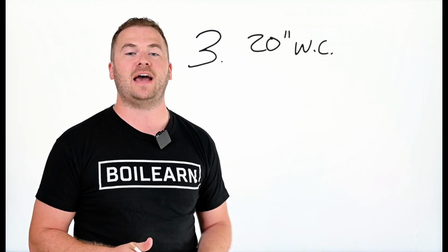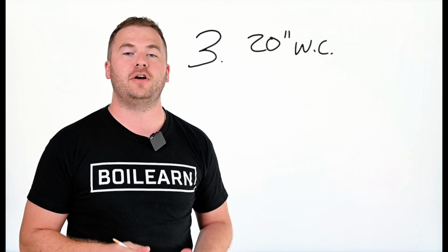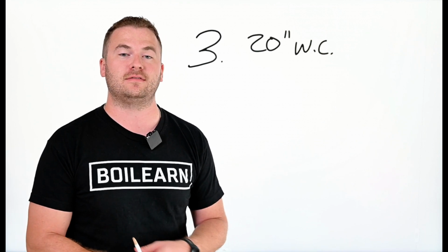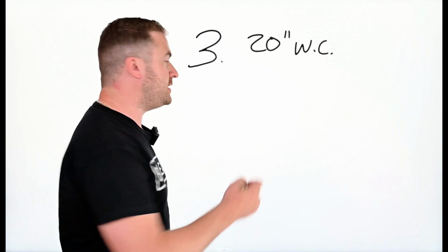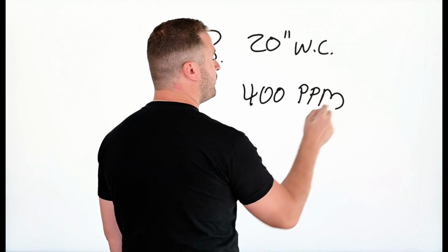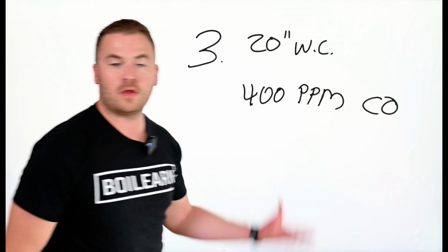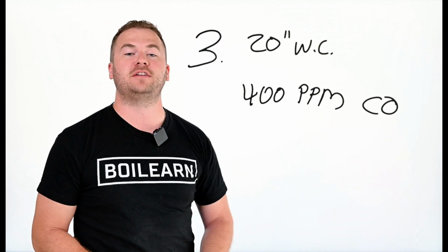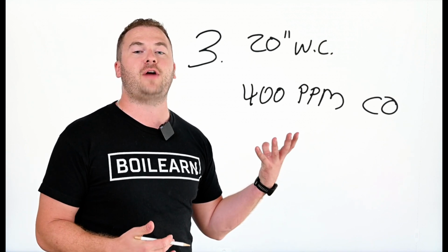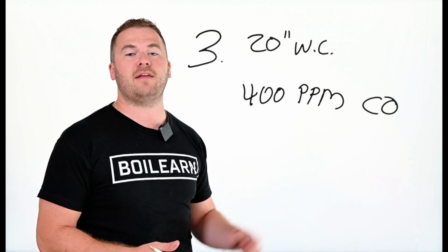for the inlet of the gas train, we're going to slowly lower the inlet gas pressure while the burner is firing, with a combustion analyzer that is monitoring the flue gas. When we start seeing unstable combustion or higher than 400 ppm, parts per million, of CO, that is going to be our low gas pressure set point. But we always have to remember that the bare minimum was the second criteria, and that is no less than 50% of the main manifold pressure.